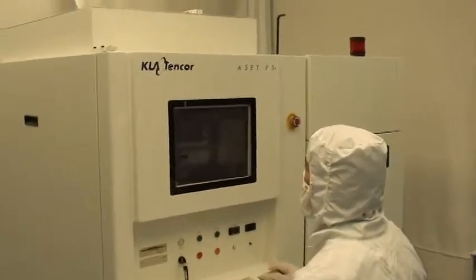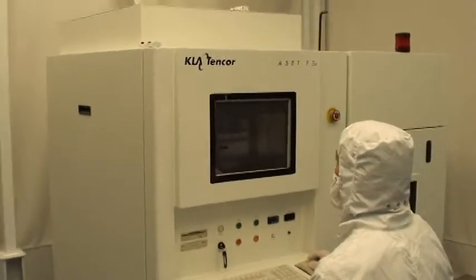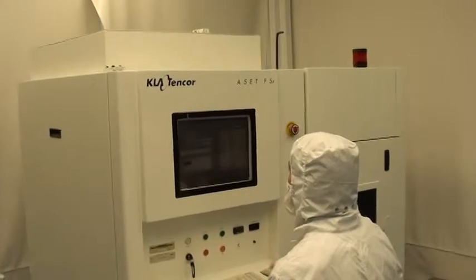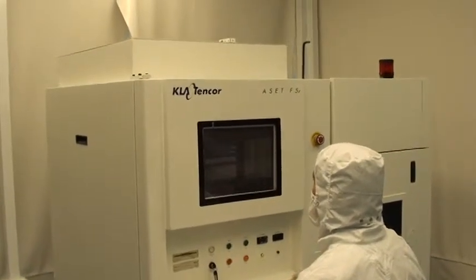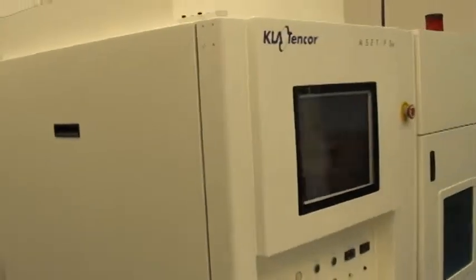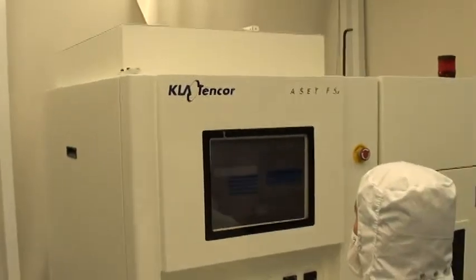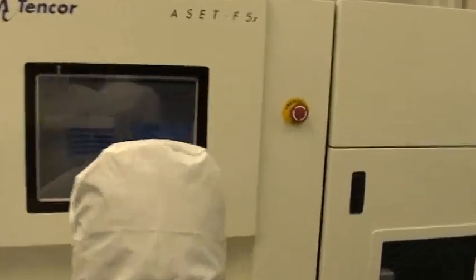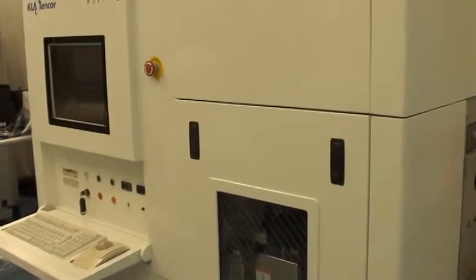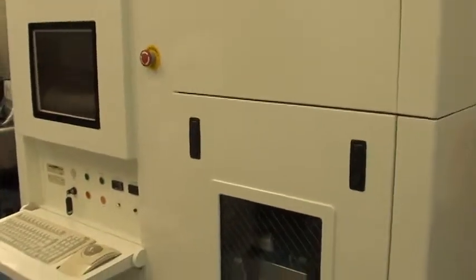This tool has undergone major refurbishment where we have changed and replaced all consumables, which includes Xenon lights and the lamp window glass cover. We have also replaced the paraboloid assembly with a new one, and the keyboard trackball with new. We have tested the Jaz drive and it works very well. We have also tested the power supply and all sub-assemblies.